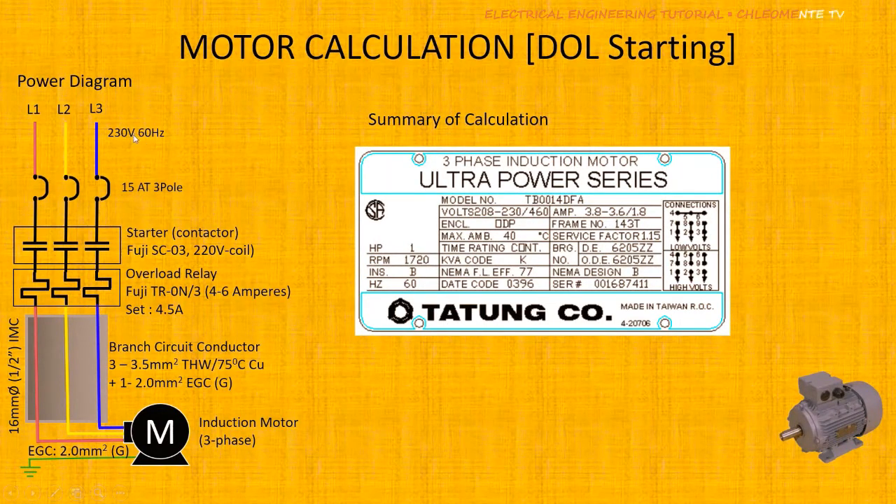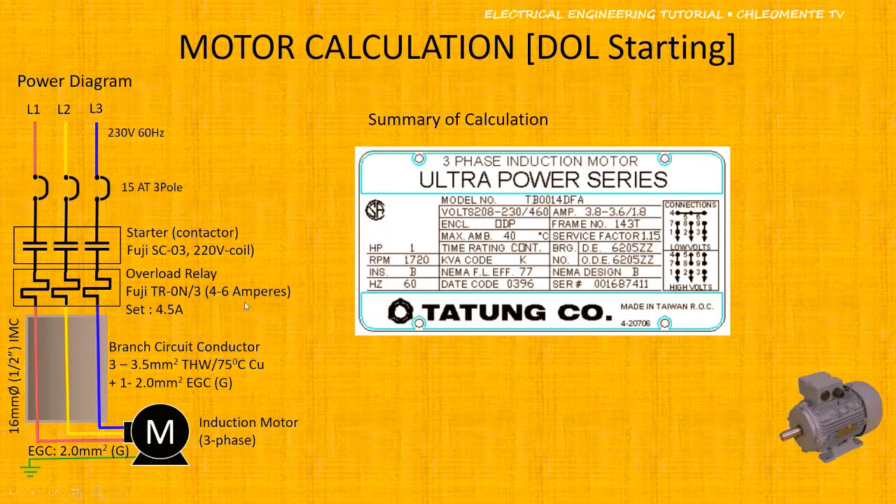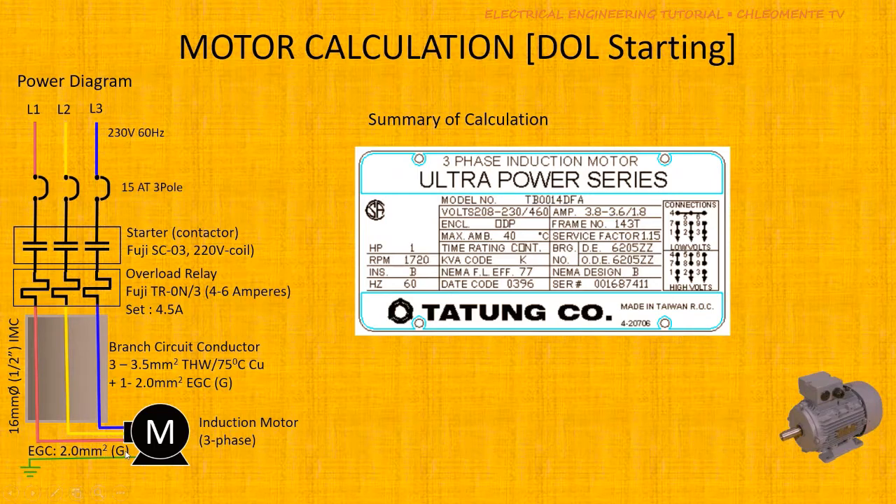Summary of calculation for a 230V, 3-phase, 60Hz system: we sized a 15A, 3-pole inverse time delay circuit breaker; a FUJI SC03 magnetic contactor at AC3 with 220V coil; a FUJI TR-0N 3-element overload relay set at 4.5A maximum (approximately 45% setting); branch circuit conductors of 3 × 3.5mm² THW 75°C; EGC of 2.0mm²; and a 1/2-inch IMC conduit.